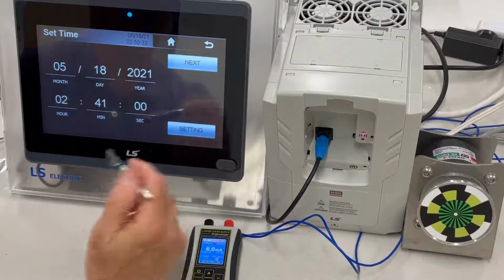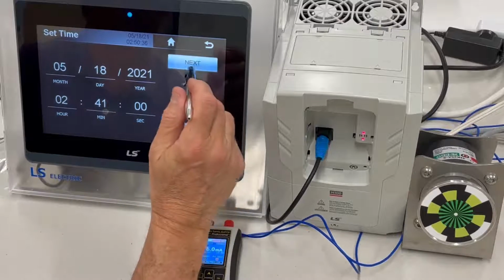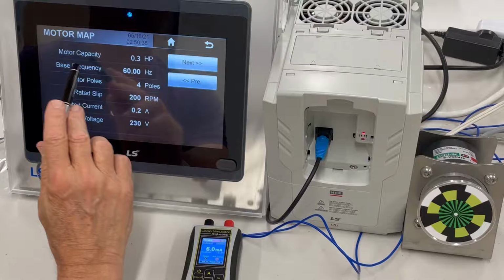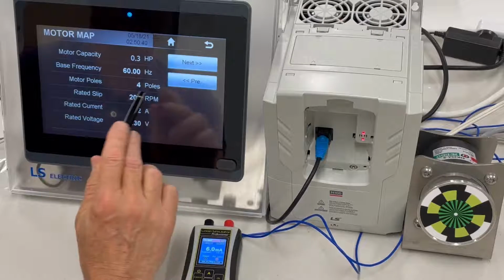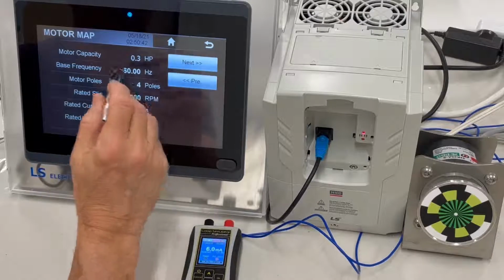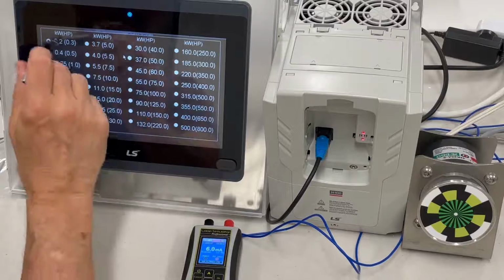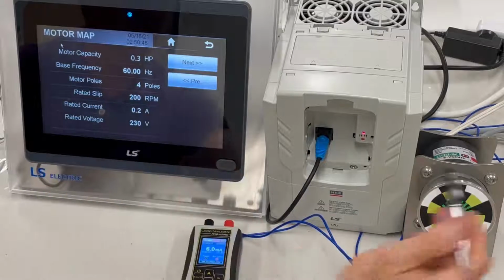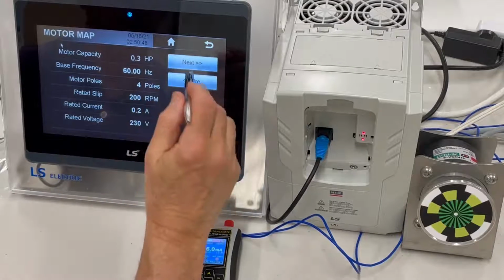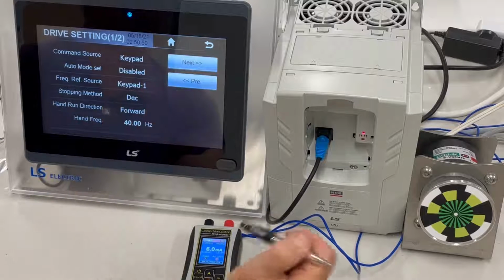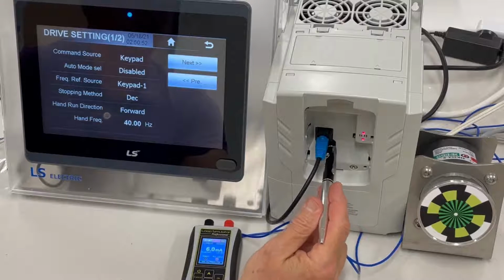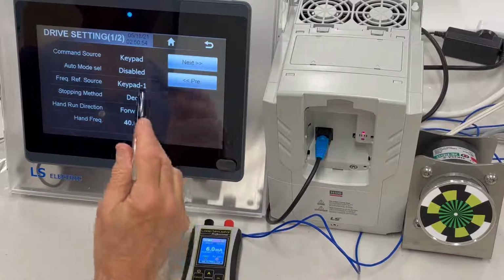So here's the date and time. I set that up earlier so you wouldn't be bored with me doing that. Here's the motor capacity, base frequency, the poles, all that stuff we set up. Very easy to do. And we have a motor map. You select a motor map, and then based upon the nameplate of the motor, you enter your data. Command source is keypad, because remember, we're connected to the keypad port, so that's where it is.